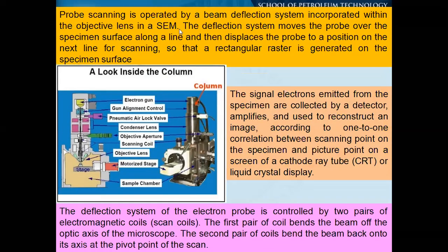We can use two types of sources — one is a thermionic source and one is a field emission source — for generating the electron beam. Probe scanning is operated by a beam deflection system incorporated into the objective lens of the SEM. The deflection system moves the probe over the specimen surface. We put the specimen in the specimen chamber, and we can also move the specimen.